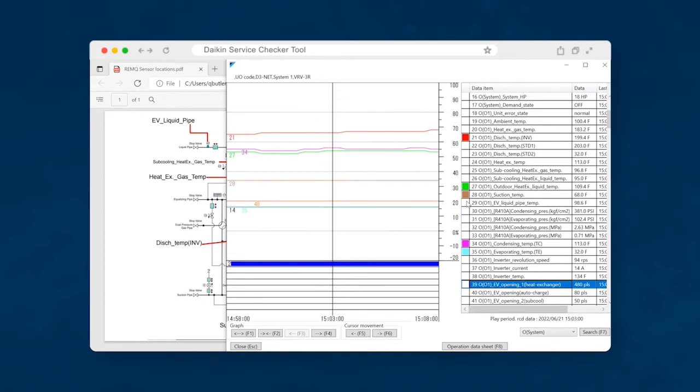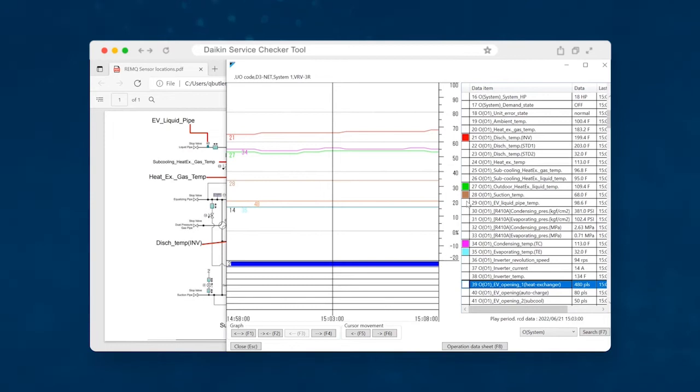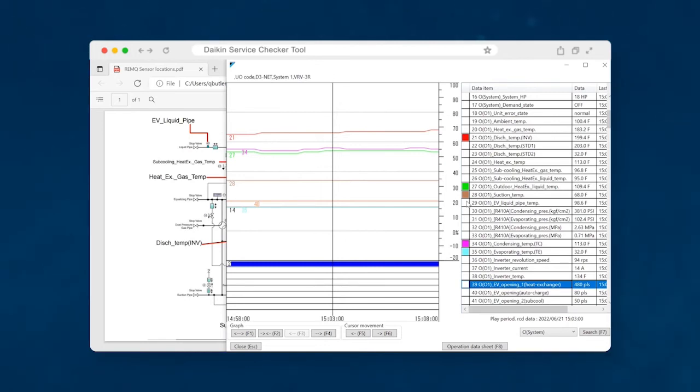And we've talked about the upper range, the refrigerant shortage, but let's say that you go out on a job and the discharge superheat is below that 27 degree threshold. And that keep in mind, whenever you're taking these readings, the system needs to be stable and it needs to have been running for a little while, 15, 20 minutes, at least stable operation, before you go benchmarking these numbers.